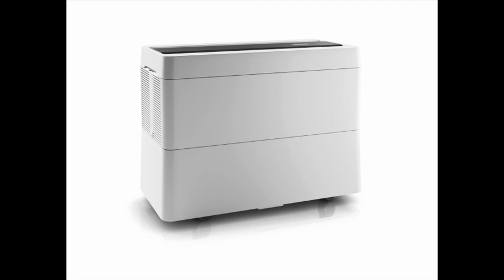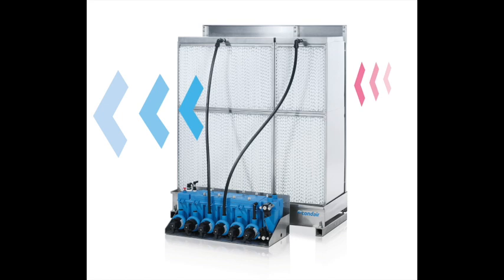Okay, Dave, you mentioned cooling there with cold water humidifiers? Yeah. Okay, so how does that work? Can humidifiers be an alternative to aircon? Well, not really a replacement for aircon, but they can have a place. Whenever water is evaporated, an evaporative cooling effect happens. Now, if this is useful, like in a hot factory, then it's a really nice bonus, and you can help lower cooling costs. But often we're humidifying places in the winter, because indoor air is much drier then, and this isn't the season we normally need more cooling. So in fact, cooling from a cold water humidifier will often need to be counteracted rather than enjoyed.